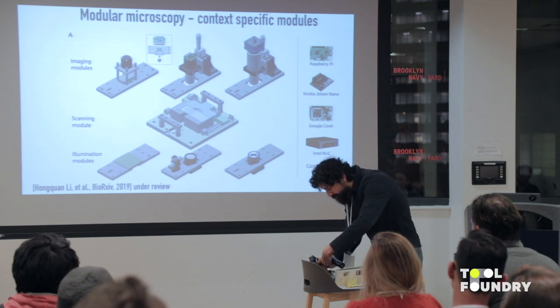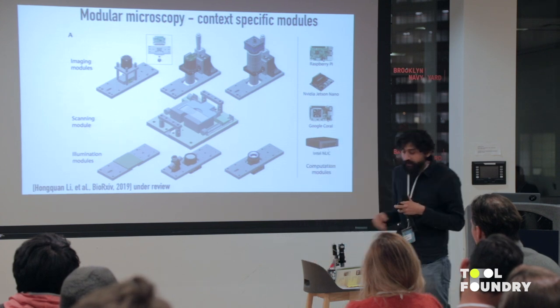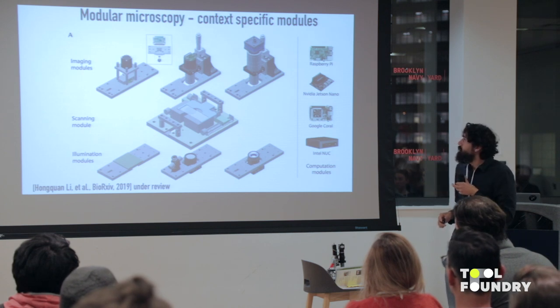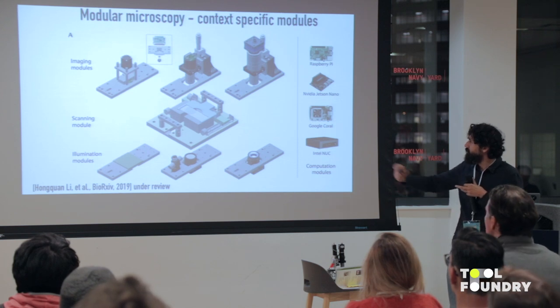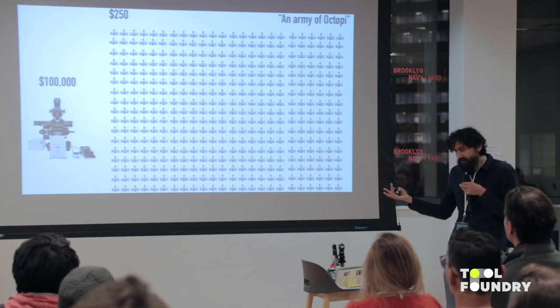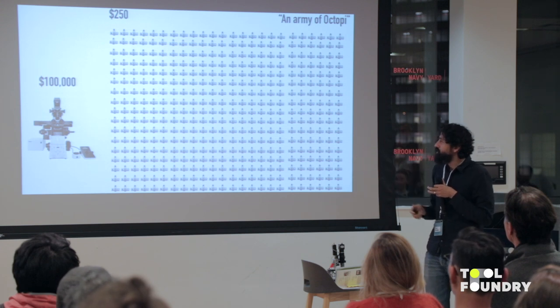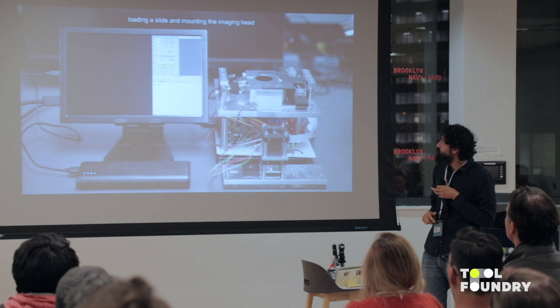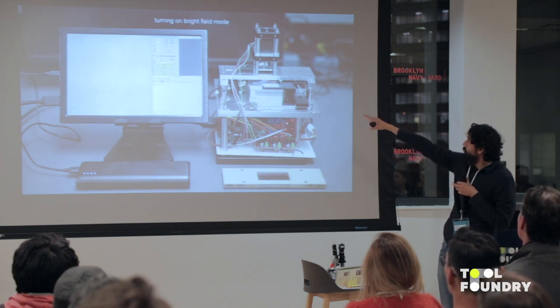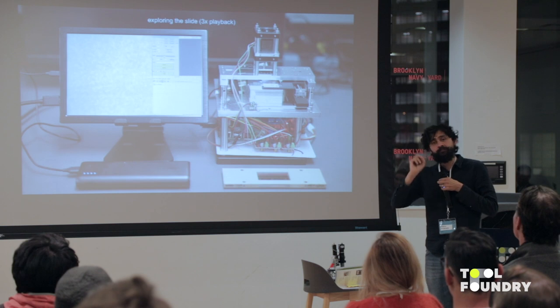It's called Octopi not because it has tentacles, but because it's completely modular, reconfigurable, and has multiple heads. The microscope reconfigures based on sets of computational modules and imaging modules — it is a little robot. We released this tool this year as open source; all the files and much of the data are online. We built it for a cost of around $250. The competitor in the field that does something similar in an automated manner costs around $100,000 — that's literally 400 Octopis. You'll see a demo downstairs. It operates on a cell phone charger. You put in a blood smear, turn it on, and it starts autofocusing and scanning.